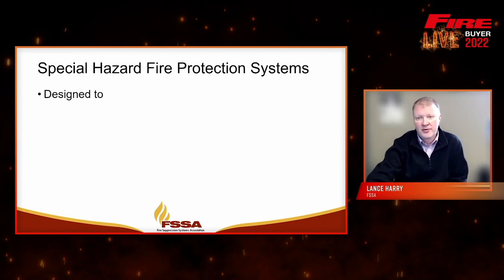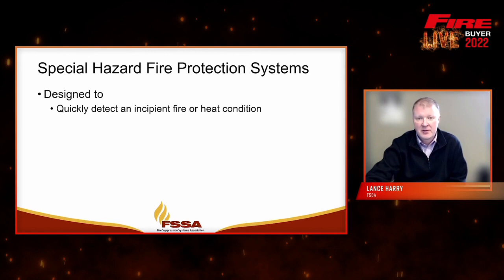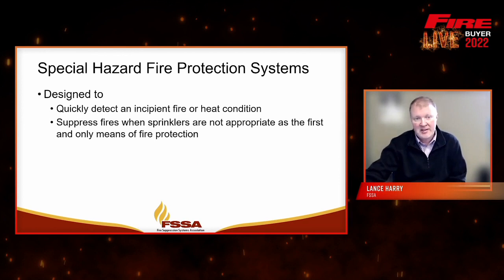So what is a special hazard system designed to do? Well, it's a number of things. Quickly detect an incipient fire or a heat condition, so we want to protect and detect the potential incident very early on. If you can detect it early and suppress and extinguish the potential fire early, you're minimizing damage and downtime, which is one of the fundamental objectives of these systems. You're trying to detect and suppress the fire early, particularly when sprinklers may not be the best first line of defense for your fire protection strategy.